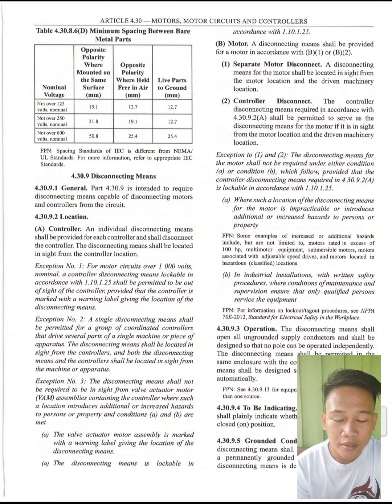Next is exception number 3. The disconnecting means shall not be required to be in sight from the valve actuator motor assemblies containing the controller where such a location introduces additional or increased hazards to a person or property and conditions A and B are met. First, the valve actuator motor assembly is marked with a warning label giving the location of the disconnecting means. Second, the disconnecting means is lockable in accordance with 1.10.1.25.